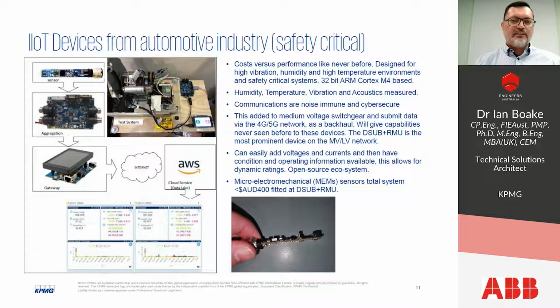So what I want to talk about is devices out of the automotive industry which have significantly dropped in price. These are very, very powerful microprocessors and sensors. The sensors are what we call micro electromechanical sensors, fairly low cost but very high precision. Those microprocessors with those sensors put together in devices can be fitted to distribution subs as well as ring main units. Such a system would only cost a couple of $100 and then give great visibility via onboard fast Fourier transforms around acoustic, representing potential arcing, as well as vibration. They measure humidity, temperature, atmospheric pressure, audible noise, explosions, etc., with high fidelity microphones.